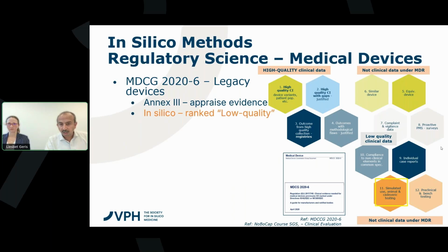What is most important in this drawing is that if you are looking into a high risk medical device, for example, class 3 implantable devices or class 2B implantable devices, then in that case, you cannot go below 4. So you have to have only the top 4, and notified bodies don't have any obligation to say, I will make my decision by evidence number 11 and 12, is what you see from practice. So it is important to note where this notion of low quality evidence comes from. This is one source that we think is possibly giving rise to this notion. What is low quality and high quality evidence within regulatory procedures?